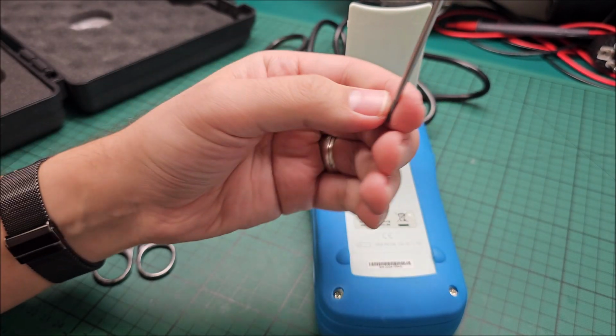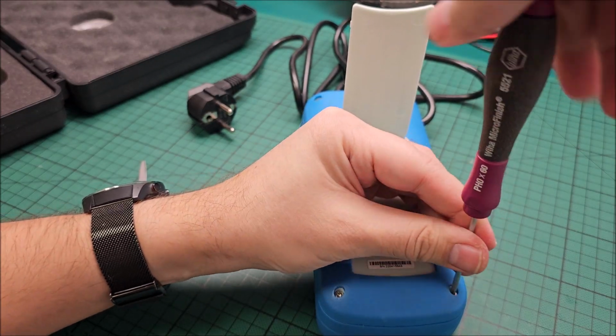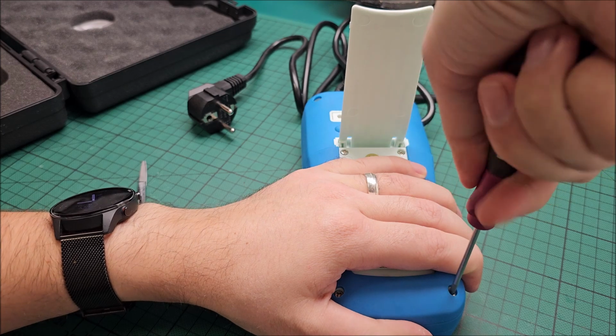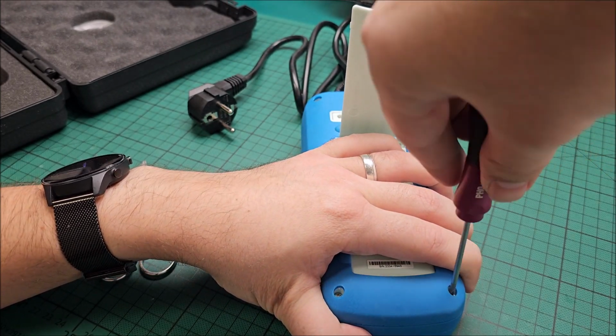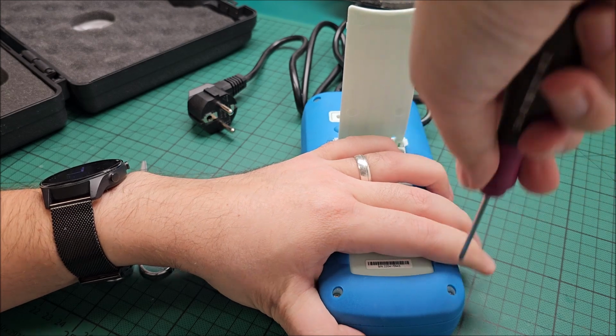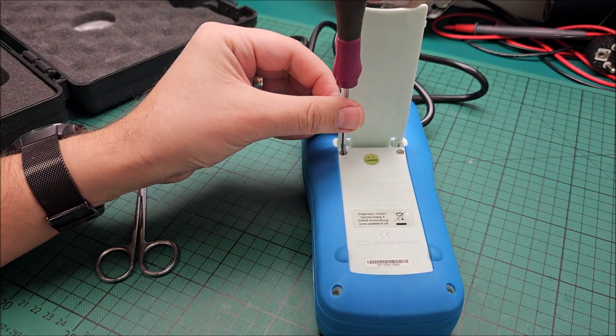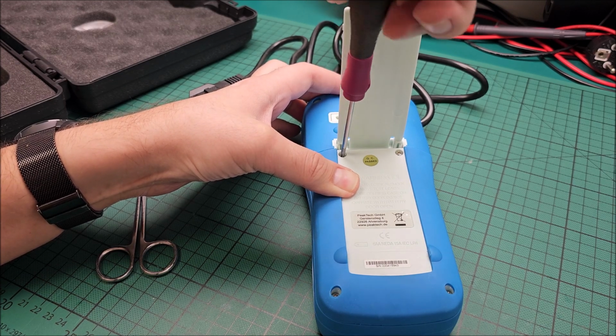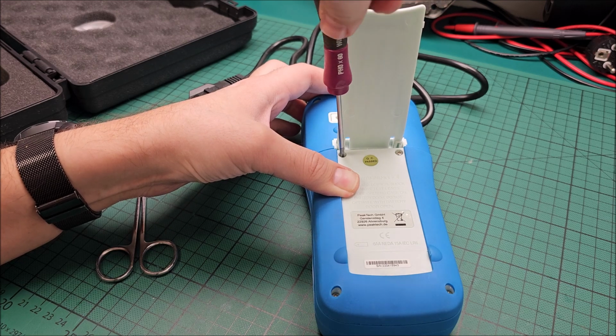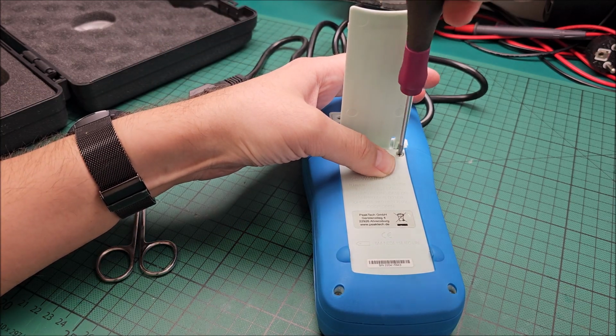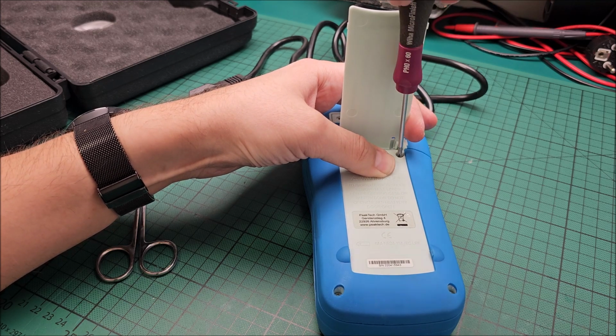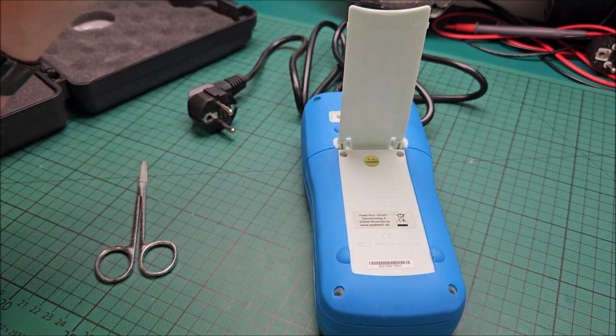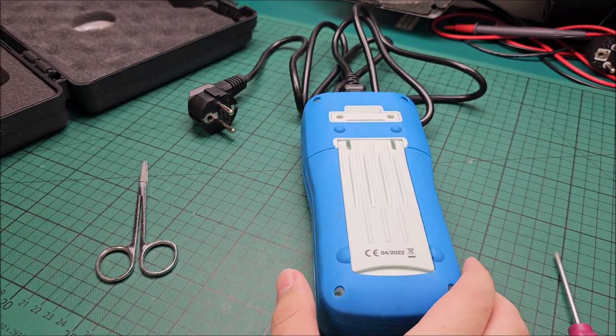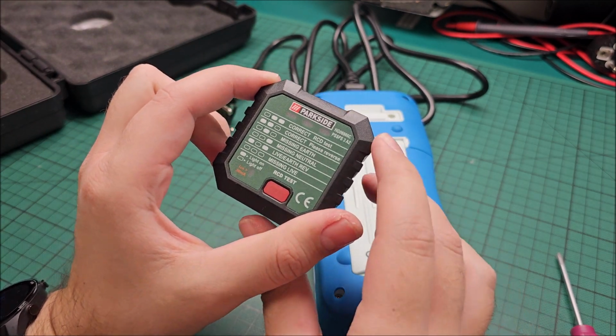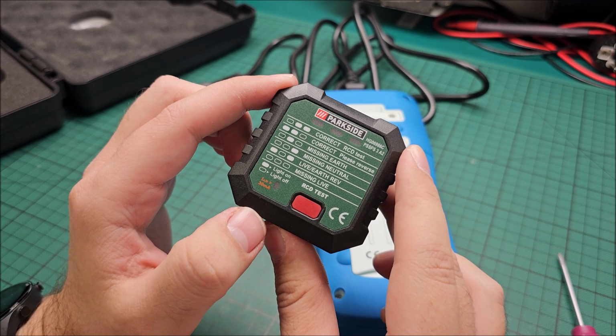This house has a 30 milliamp tripping current RCD. That's for the whole house. When we installed a bathtub with a pump in it, so basically the type that massages you, the instructions said, I don't know, I think a 15 milliamp RCD. So obviously I couldn't put one of those for the whole house, could I? And at that point I added one special for the bathroom for that tripping current that was required. Then I tested it with this little guy. Well, surprise, the 30 milliamp tripped and the 10 milliamp did not trip.